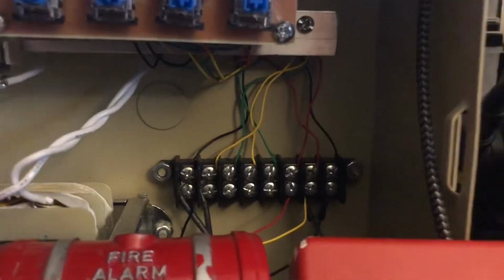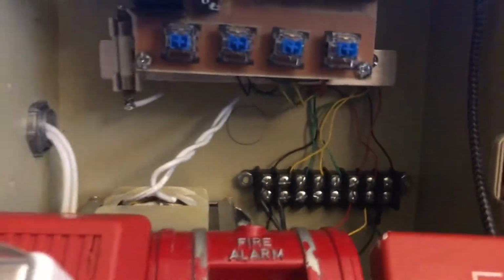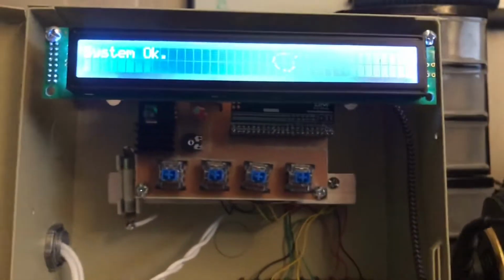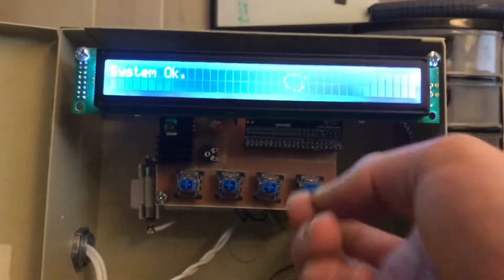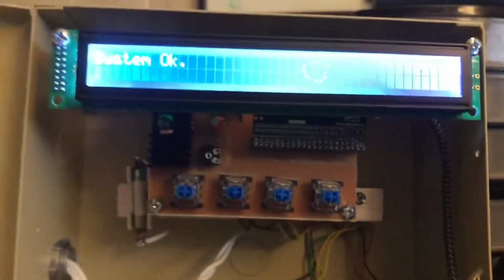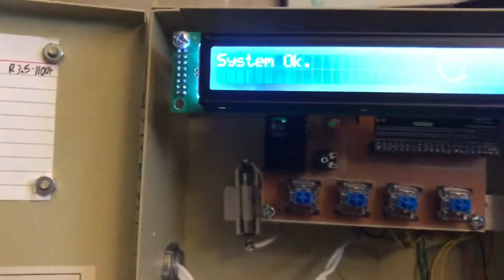This panel has two NACs, 5 zones, 2-wire support, solid-state 2-wire support, I may add. Currently, it has two NACs that are relay-based. When I'm finished, the two NACs will be solid-state transistor-based, and the two relays will actually be relays, you know, for controlling external stuff.